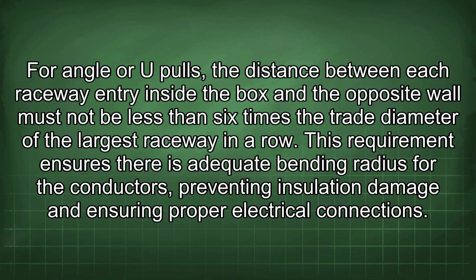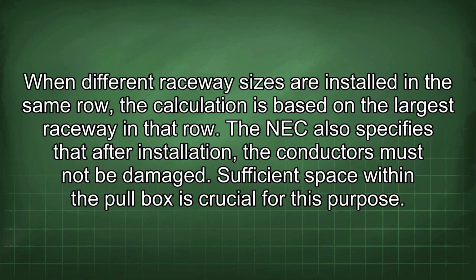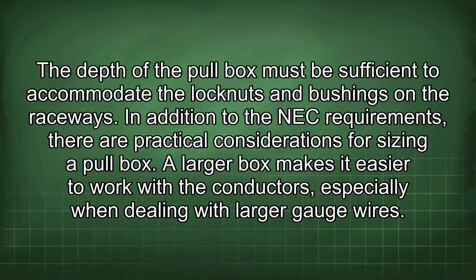For angle or U-pulls, the distance between each raceway entry inside the box and the opposite wall must not be less than 6 times the trade diameter of the largest raceway in a row. This requirement ensures there is adequate bending radius for the conductors, preventing insulation damage and ensuring proper electrical connections. When different raceway sizes are installed in the same row, the calculation is based on the largest raceway in that row. The NEC also specifies that after installation, the conductors must not be damaged. Sufficient space within the pull box is crucial for this purpose. The depth of the pull box must be sufficient to accommodate the lock nuts and bushings in the raceways.